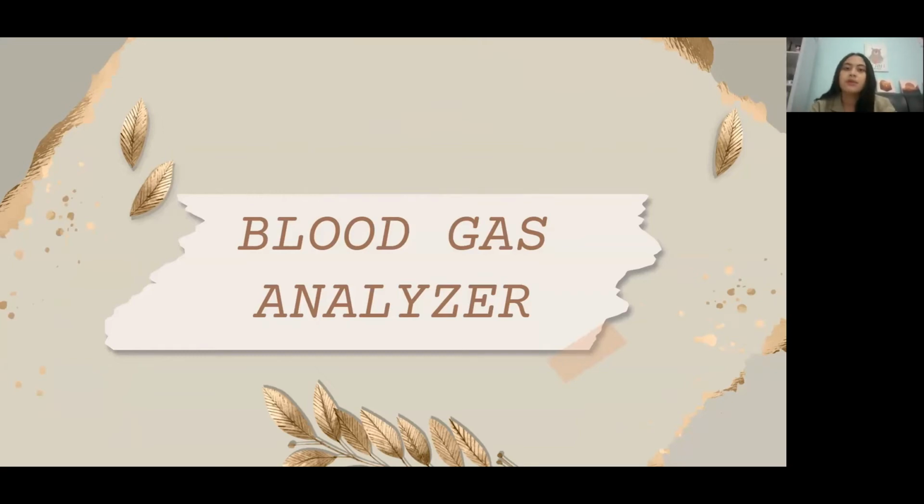The working principle of blood gas analyzer is that this device uses electrodes to determine pH, partial pressure of oxygen, and partial pressure of carbon dioxide in the blood. The whole blood sample is placed in the tube, reaction cuvette, or test strip, then loaded into the analyzer. Next, the operator can choose the test to be performed using a keypad or connected computer.